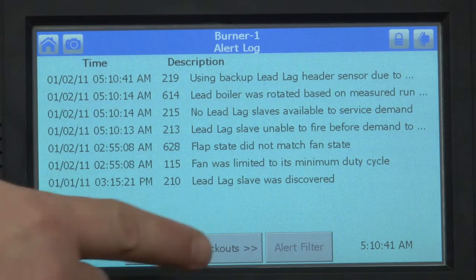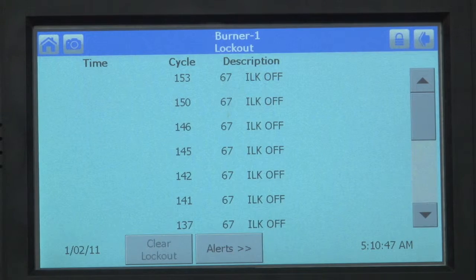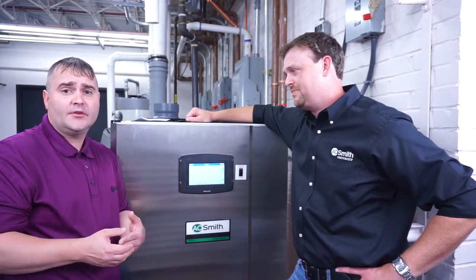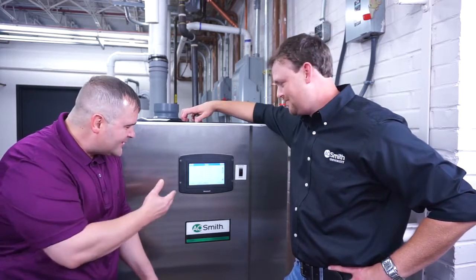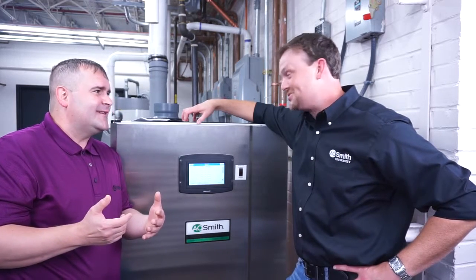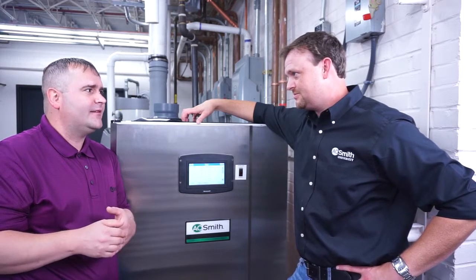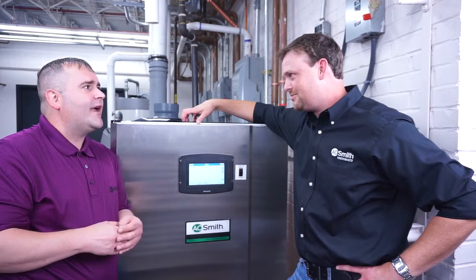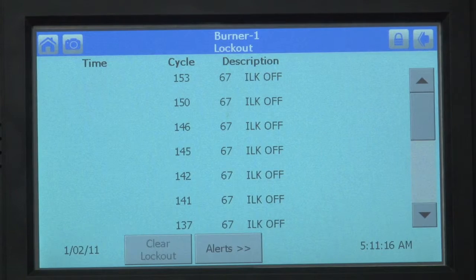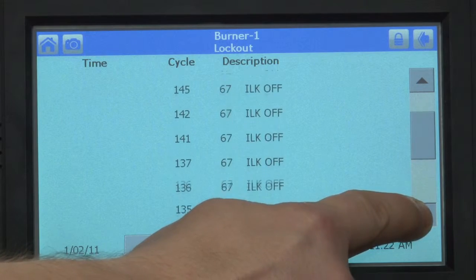In the center you'll see Lockouts — press that. These all say ILK OFF, which means something in the low-voltage control circuit, the 24-volt control string, has locked out. The reason you see this on this particular water heater is because we have the gas on a timer. After an hour or so it times out, and during training in the lab when we walk out and the timer times out, it's going to lock out on low gas. These are the actual lockouts. Using the up and down icons, you can scroll and view every single one of them.